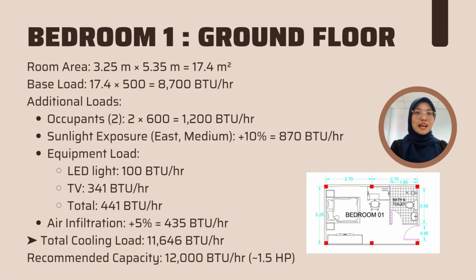Air infiltration contributes another 435 BTU. So, the total cooling load becomes 11646 BTU per hour. Therefore, we recommend a unit with 12000 BTU per hour capacity, which is approximately 1.5 horsepower.